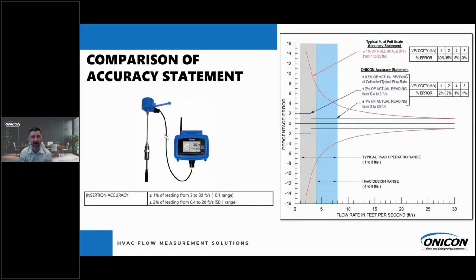And you can't talk about an ONICON product without talking about the accuracy or the performance. I like to really encourage the engineers here to think about three components when talking about an accuracy statement. What is the percentage of accuracy, what is that in reference to, and over what range is that valid for? We see this missed a lot. Yeah, I want a 1% device. Well, 1% of what? This graph here on the right demonstrates the difference between a 1% of full-scale device versus a 1% of reading device. At 30 feet per second, or full scale, they're both 1%.